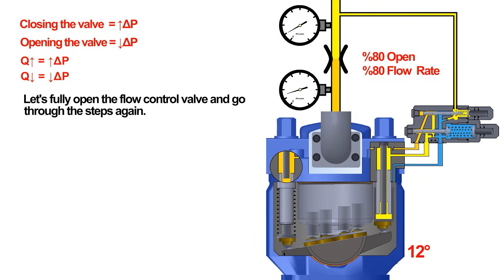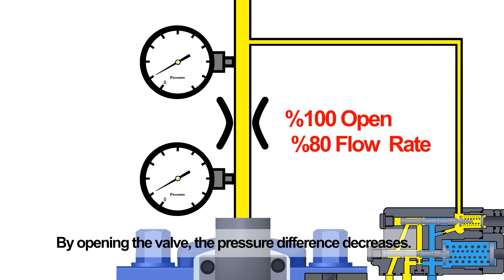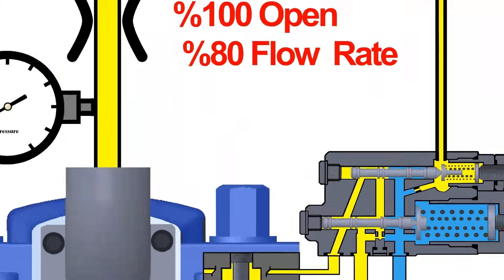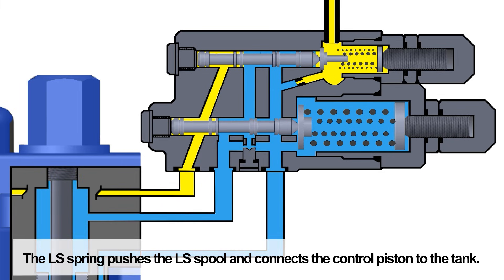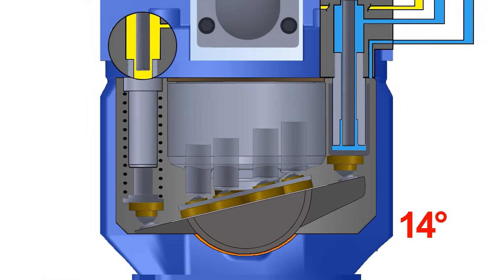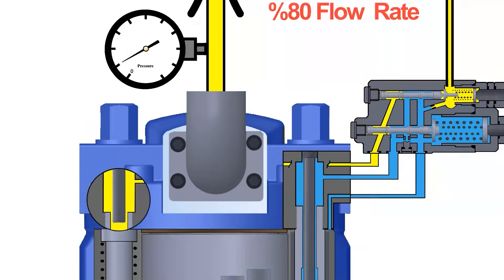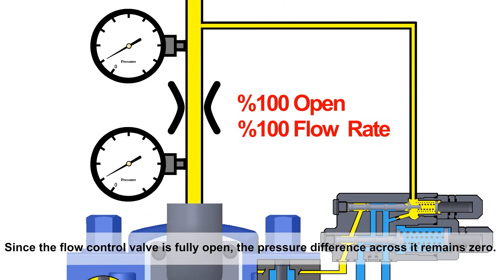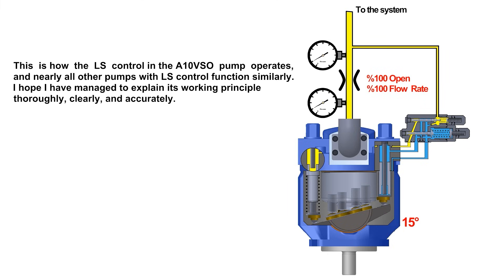Let's fully open the flow control valve and go through the steps again. By opening the valve, the pressure difference decreases. The LS spring pushes the LS spool and connects the control piston to the tank. The bias piston pushes the swash plate toward maximum displacement. Since the flow control valve is fully open, the pressure difference across it remains zero. This is how the LS control in the A10VSO pump operates, and nearly all other pumps with LS control function similarly.